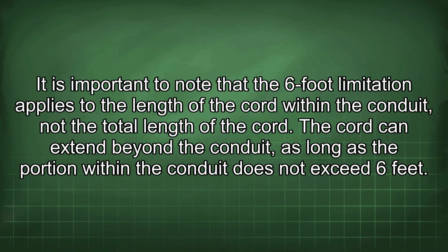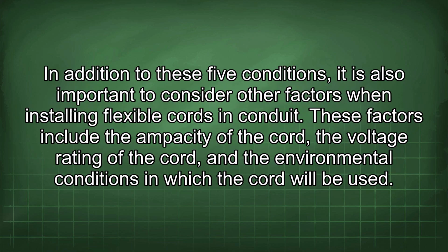It is important to note that the 6-foot limitation applies to the length of the cord within the conduit, not the total length of the cord. The cord can extend beyond the conduit as long as the portion within the conduit does not exceed 6 feet. In addition to these 5 conditions, it is also important to consider other factors when installing flexible cords in conduit.